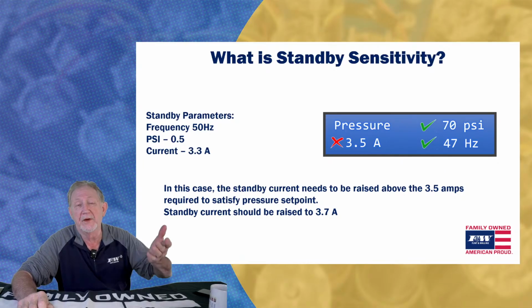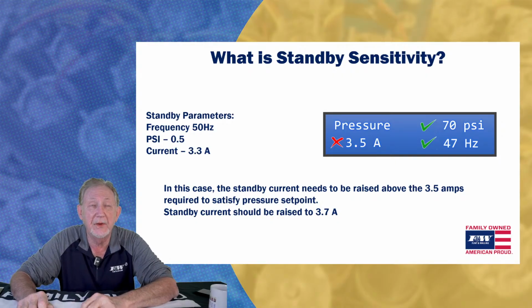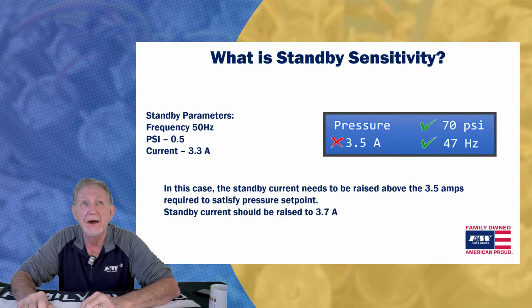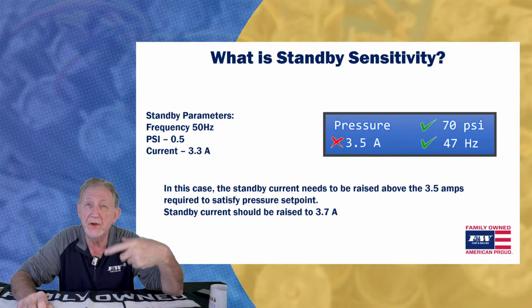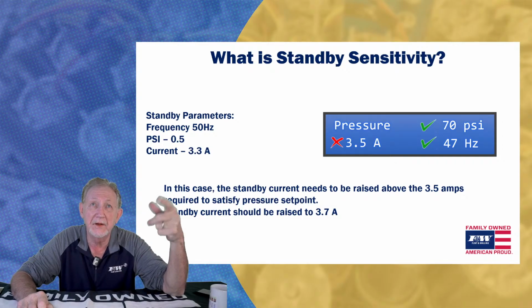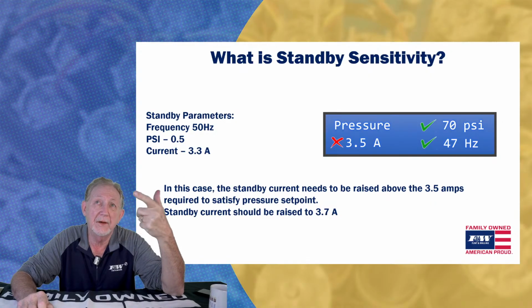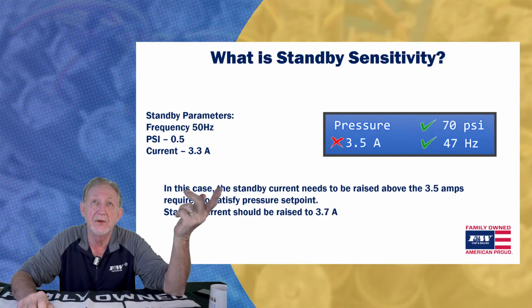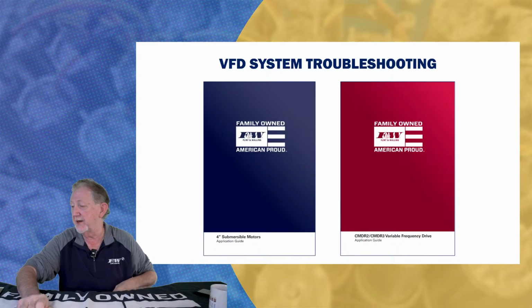So how do we do that? Well, we're going to raise that threshold on that amps. Again, you're going to go into edit. You're going to hit your up button. You're going to take it up to 3.7 amps. And now your 3.5 amps are running below that threshold, and the drive will go into standby.